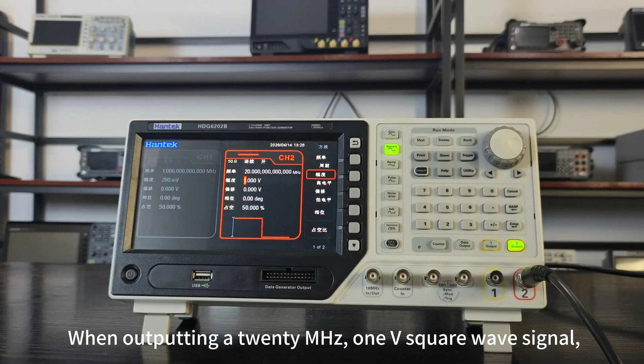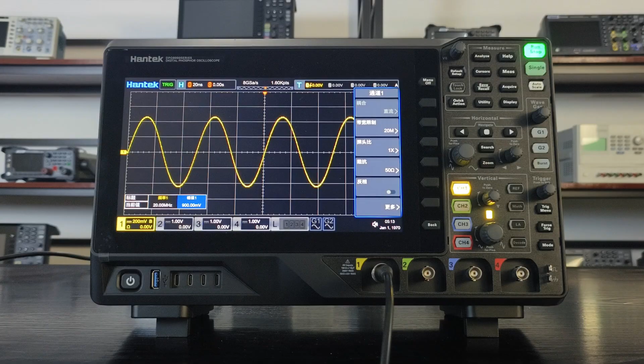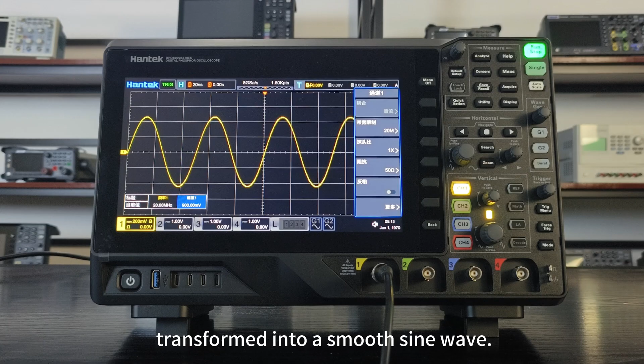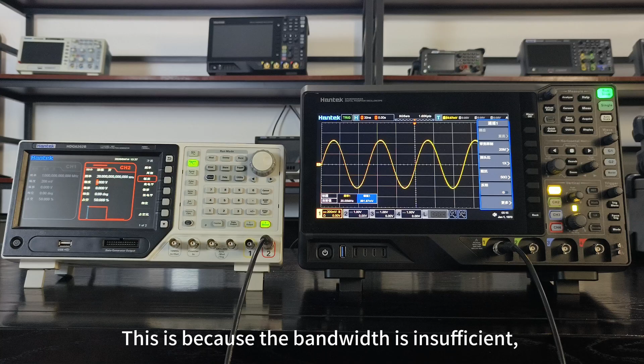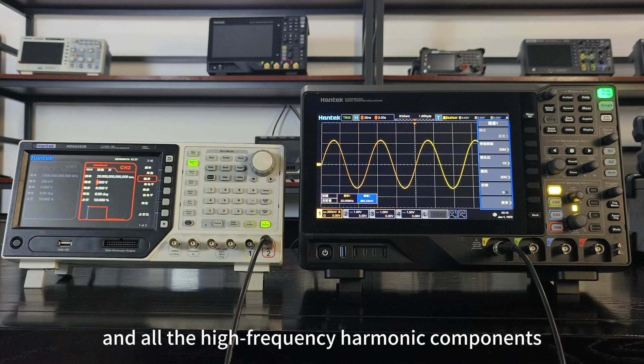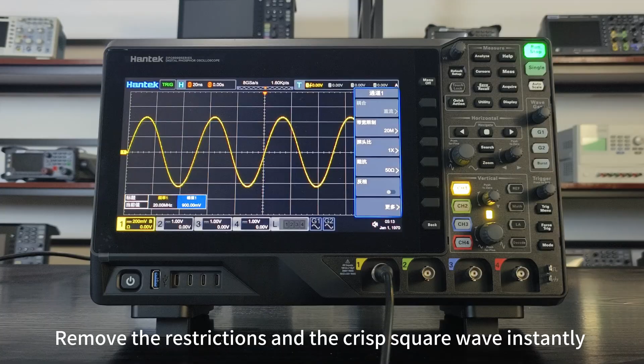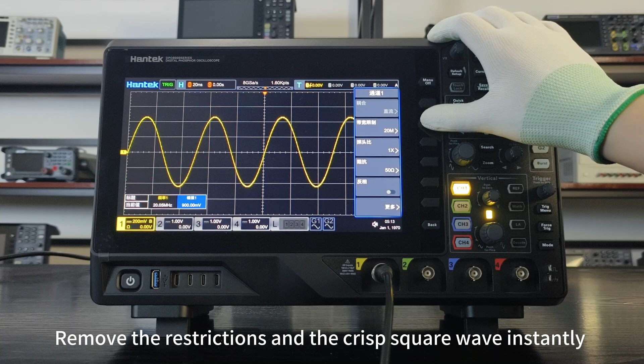Now let's look at the square wave when outputting a 20 MHz 1 V square wave signal. After enabling the bandwidth limitation, the square wave directly transforms into a smooth sine wave. This is because the bandwidth is insufficient and all the high-frequency harmonic components in the square wave have been filtered out. Remove the restrictions and the crisp square wave instantly returns to normal.